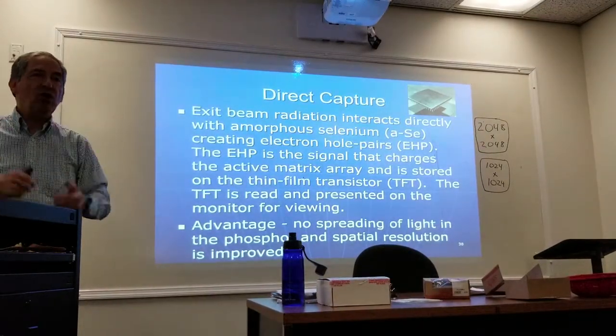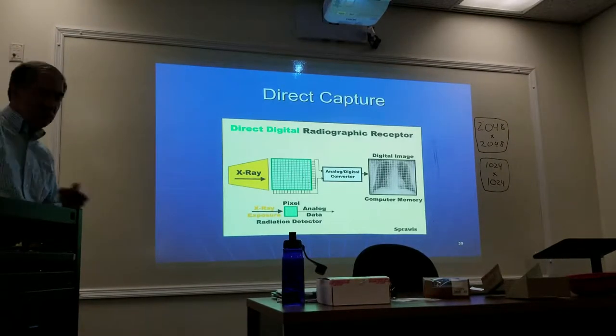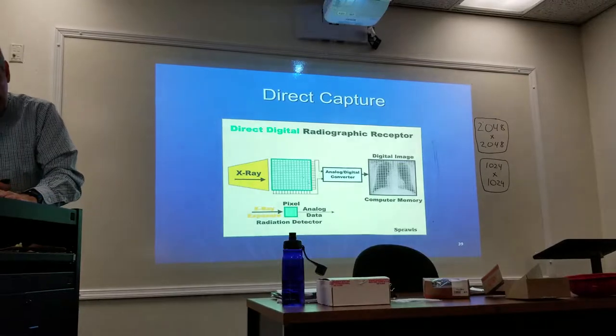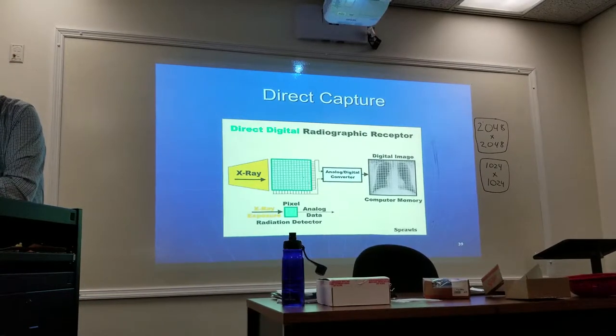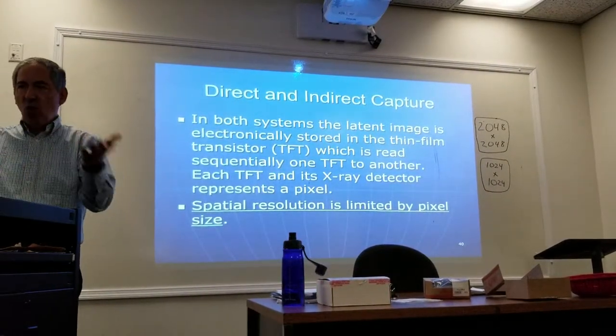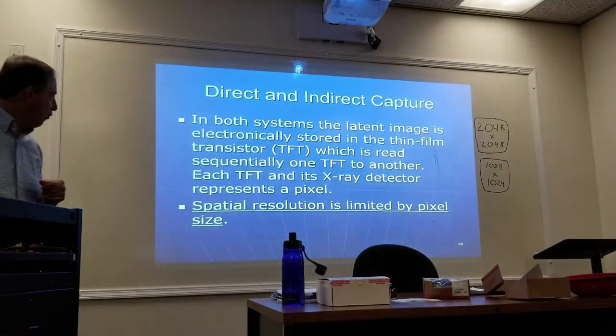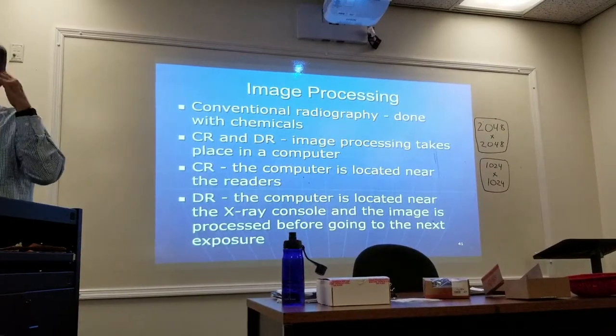With direct capture, x-rays strike this matrix of pixels and use amorphous selenium. 'Amorphous' just means uncertain shape. The image is acquired as a matrix of pixels and then converted from analog to digital. With both systems, the latent image is stored in thin film transistors. Spatial resolution is limited by pixel size.